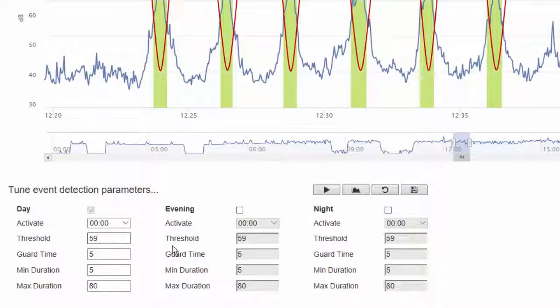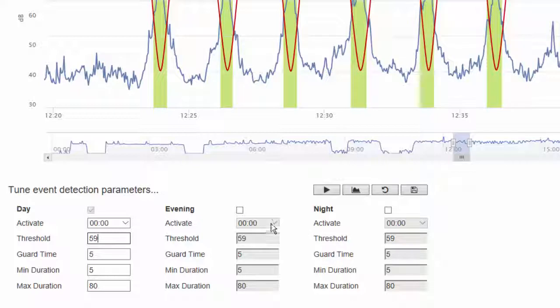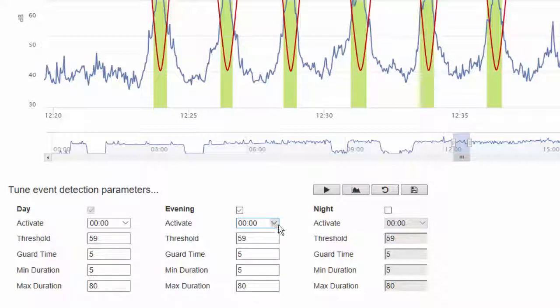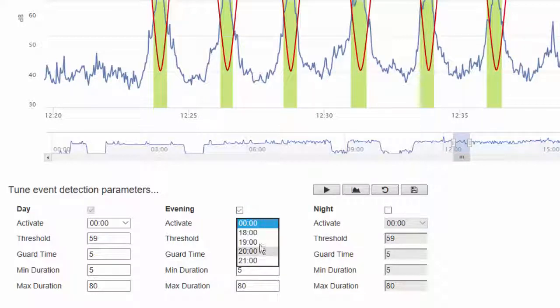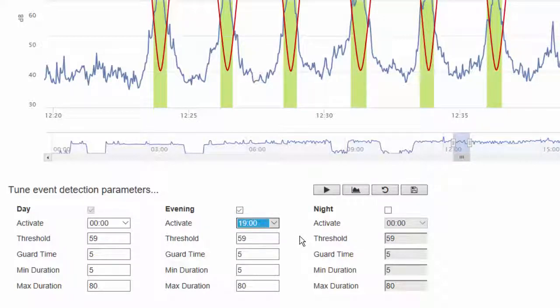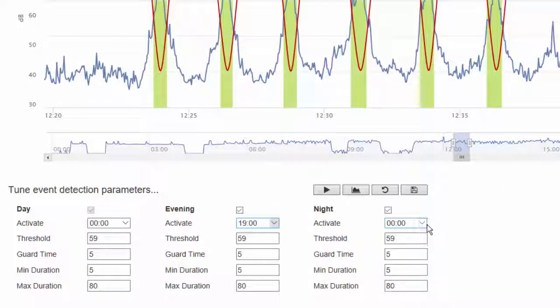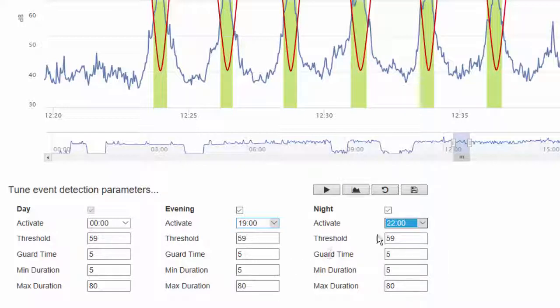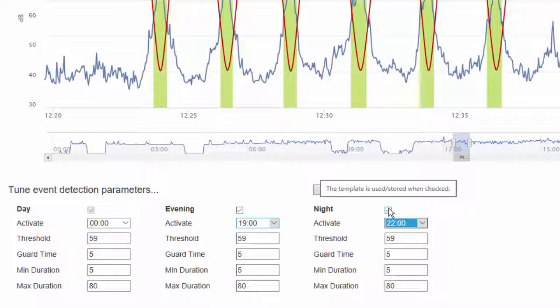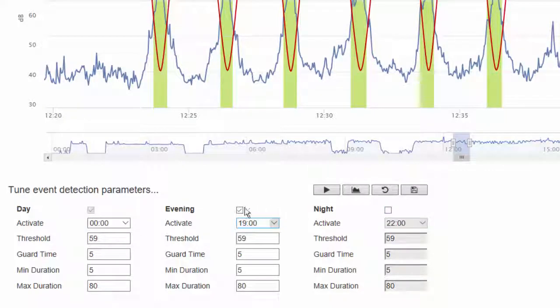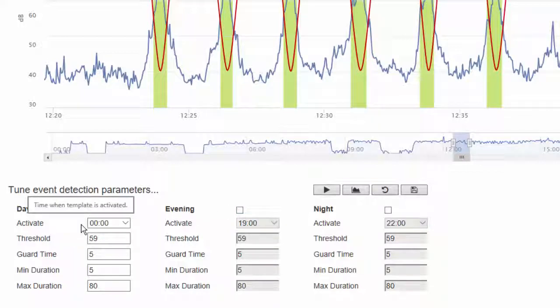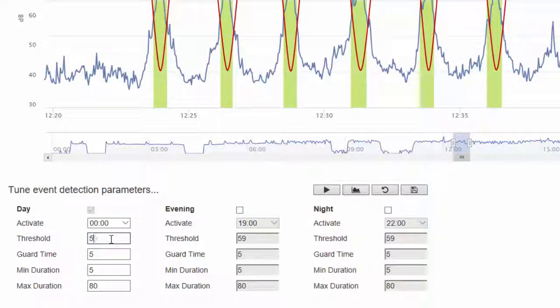For most tuning cases we advise threshold changes. The intent here is to ensure that community noise is not attributed to passing aircraft. And we do not want to raise the threshold too high to miss capturing more distant or smaller aircraft. Similarly, setting thresholds too low may result in long duration events where air conditioning or refrigeration units create a 120 second event. The aim is to find a sweet spot. And the noise event workbench allows you to model how new settings would look before you commit to actually changing them.